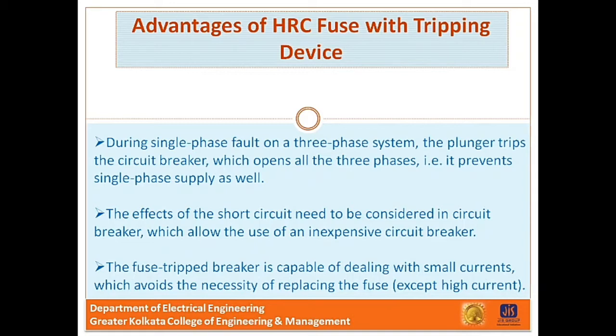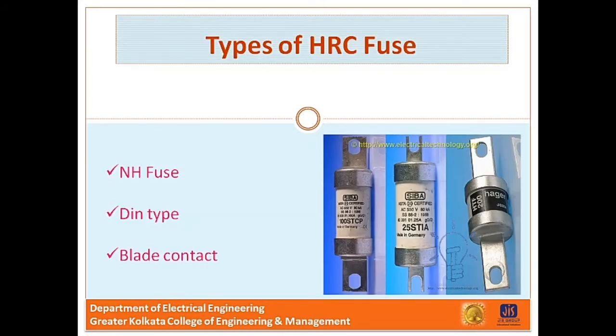Now low voltage HRC fuse may be built with a breaking capacity of 16,000 ampere to 30,000 ampere at 440 volt. They are extensively used on low voltage distribution system against overload and short circuit condition. Types of HRC fuse. There are three types of HRC fuse: NH type HRC fuse, DIN type HRC fuse, blade type HRC fuse.